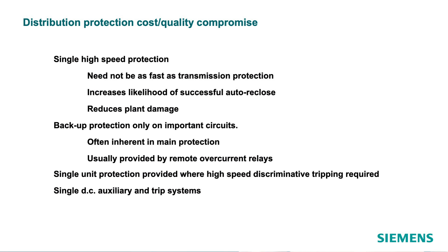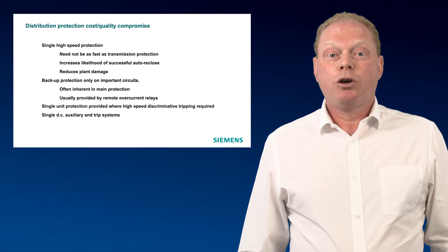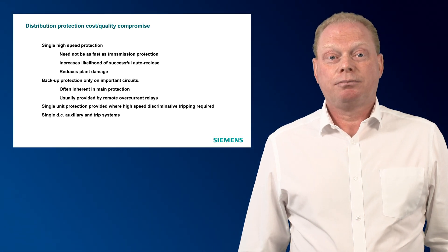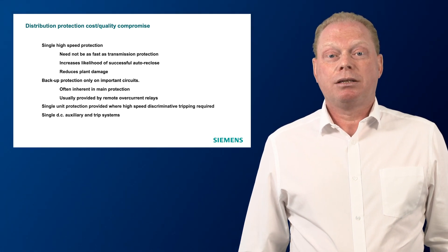In a distribution network, there is a compromise between the cost and quality of the protection system. Distribution protections are not usually duplicated as on a transmission system and as system stability is not a major concern, they also don't need to be as fast. A single protection relay is often used per circuit with integrated backup protection. Further backup protection is provided by remote overcurrent relays. Where high-speed discriminative tripping is required, this is usually provided by single unit protection such as a transformer differential device.